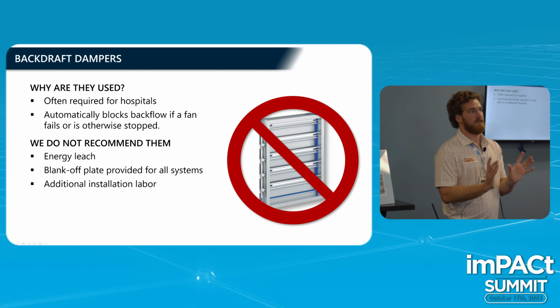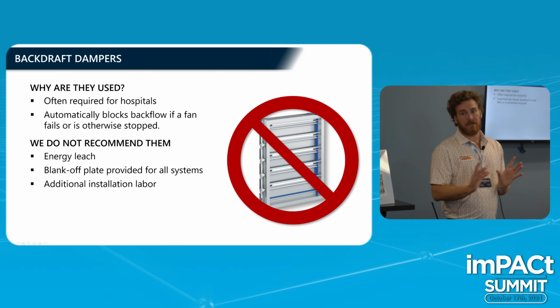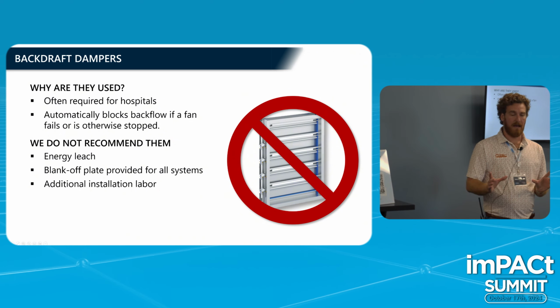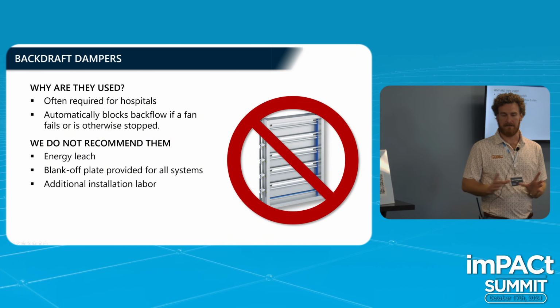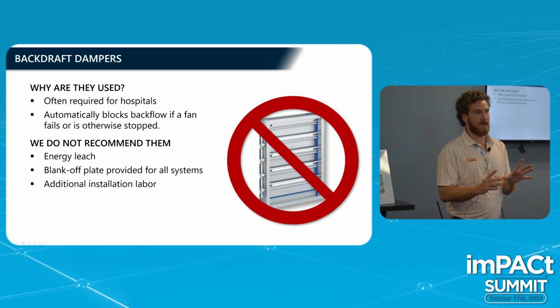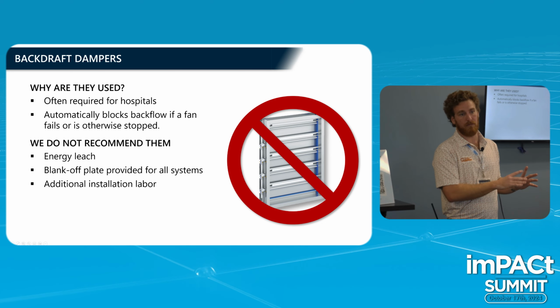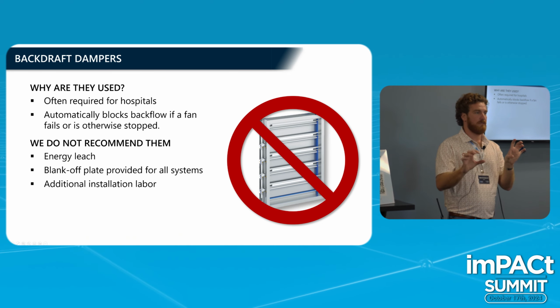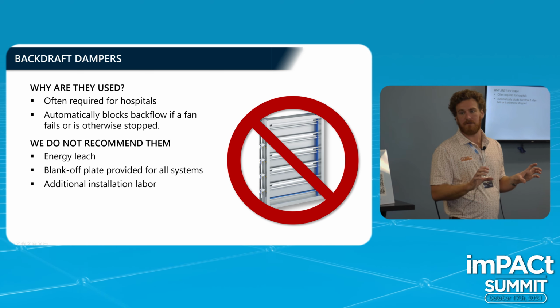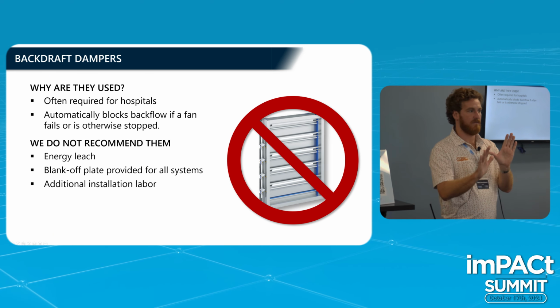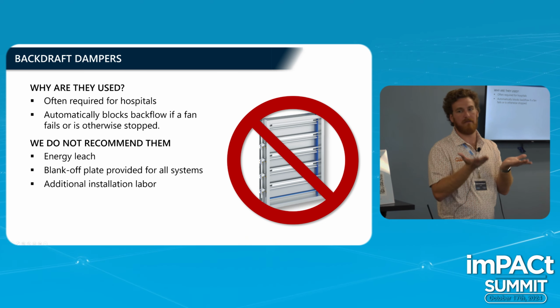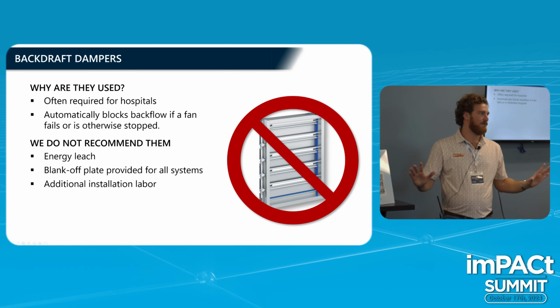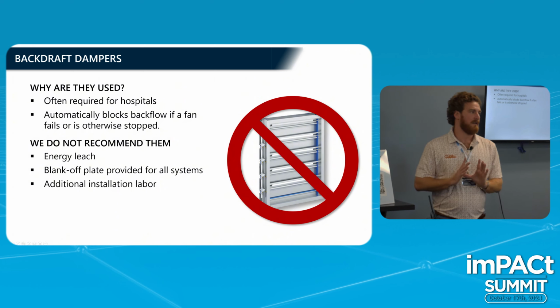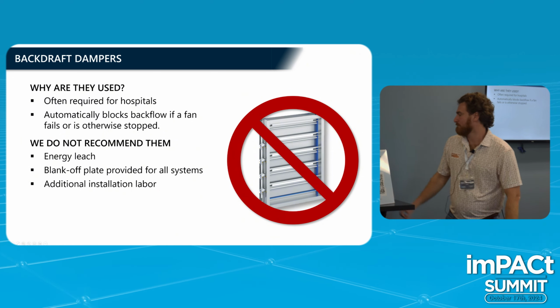There are certain situations though where you have multiple control panels in an airstream. Let's say you have one of those massive systems where we couldn't fit all the quick connect boxes and all the electrical on one control panel, and you have 2 control panels. You probably would want to use dampers in that situation, just in case there's a difference in the ramping up of the 2 units. But 99% of the time, you're going to have 1 control panel, and you're not going to want to use dampers.